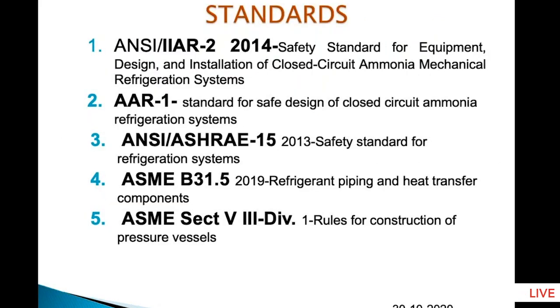Now, when we design these refrigeration systems and vessels, we follow certain standards. I am now defining all the standards which are used for designing of these vessels. The first one is ANSI/IIAR, that is American National Standards Institute, stroke IIAR. IIAR means International Institute of Ammonia Refrigeration. This is a safety standard for design of equipment. The next important standard: I am very happy to inform you that up till now in India there was no standard available, but we have designed the AAR-1 standard, and I am also happy to inform you that Bureau of Indian Standards has accepted it, and it is under printing by BIS as a government standard. So it will become mandatory for all ammonia plants, and the quality of ammonia plants will improve substantially.